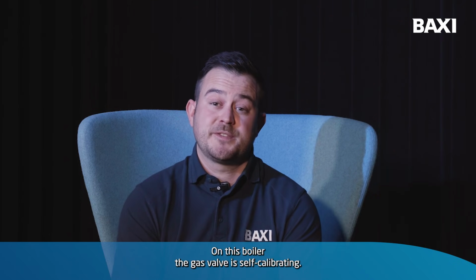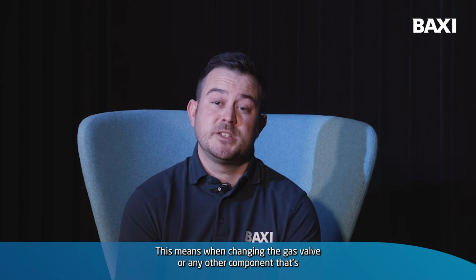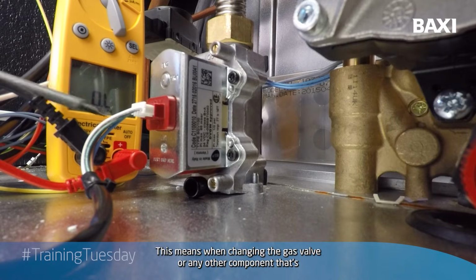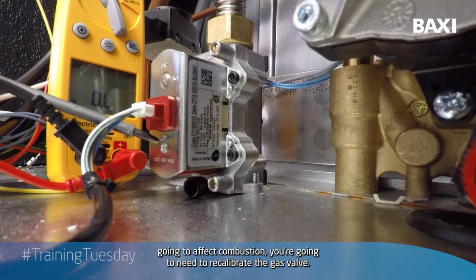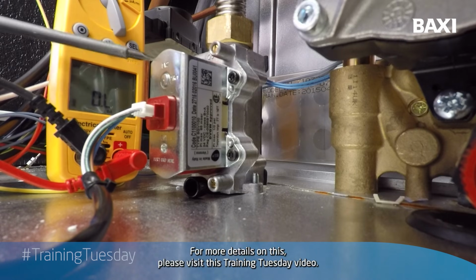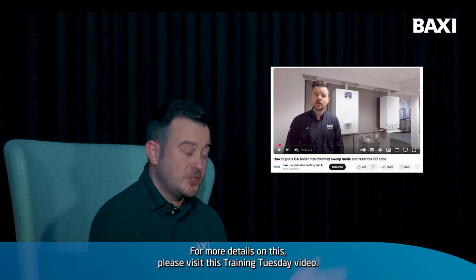On this boiler, the gas valve is self-calibrating. This means when changing the gas valve or any other component that's going to affect combustion, you're going to need to recalibrate the gas valve. For more details on this, please visit this Training Tuesday video.